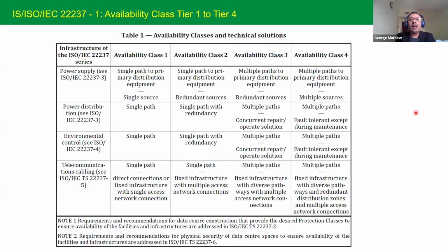So class 3 is what is called a concurrently maintainable data center, which has 2 independent paths of power and cooling to the onward equipment with the n plus 1 configuration. At the load side, we will have 2 paths of power, path A and path B, from the transformer onwards towards the IT load, and cooling will come until the fan wall unit. Let's say there will be 2 chilled water pipe circuits towards the CRAC unit. So this is called tier 3, and on the equipment side, it will be configured in n plus 1 configuration. This is called concurrently maintainable. But remember one thing: of the 2 paths, one path is live and one path is on standby.